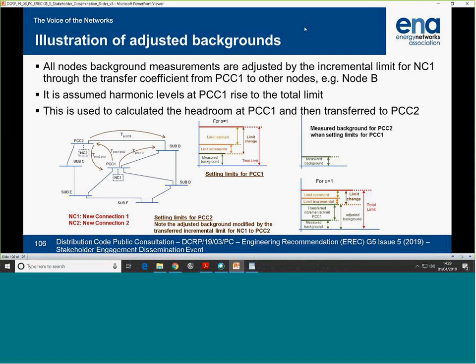This is new connection 1. I issue the limit as this. Apportionment of the headroom. Now, once I issue the limit, I assume that the background rises to the total limit I've issued, because I'm allowing new connection 1 to do that. I don't know if he does or he will, but I have to assume it because they are not yet part of the network. I assume he's going to do that. At this point, I assume the background has risen to total limit.